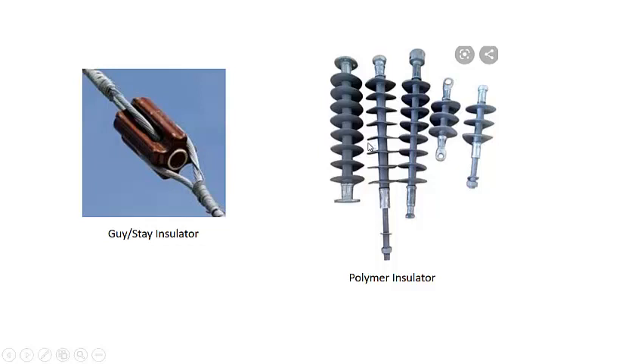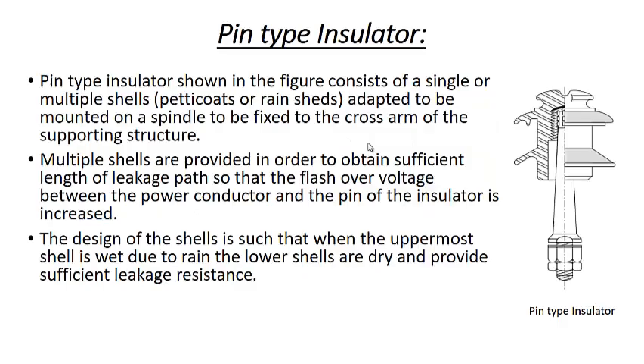Now coming to the pin type insulator, this is the cross section area of the pin type insulator. These are the petticoats, these two. This is the groove and this is the pin that is inserted over here, and this is the thread of the pin. Pin type insulators consist of a single or multiple shells. Usually we have 2 or 3 shells.